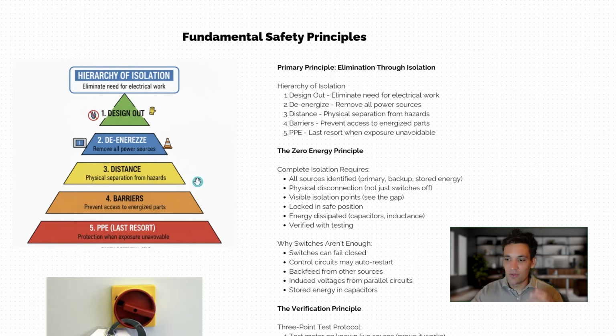Next is physical separation. If we have any live parts or components, there's a physical separation between anyone working and the hazard. If we can't maintain physical separation, we need to put in place barriers to prevent access to the energized parts. And the last resort is to actually put in place PPE or protection when doing it. This is when people have to work on live electricity lines, or when they're working around high fault currents, they'll actually wear arc flash protection suits. So that's the last resort, personal protective equipment.